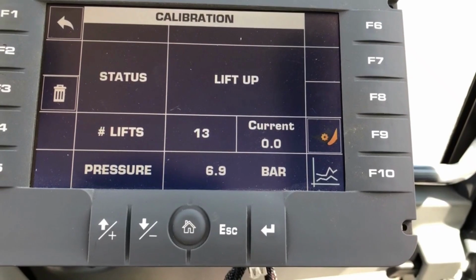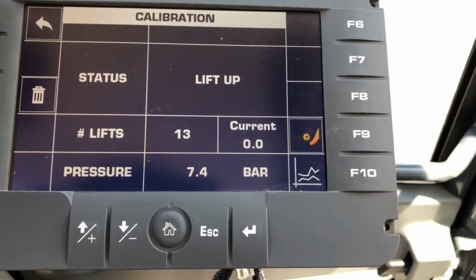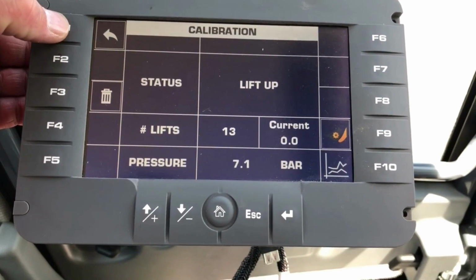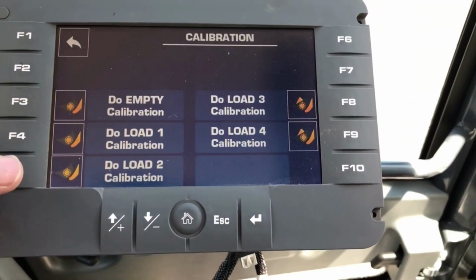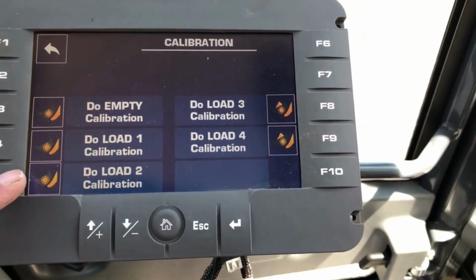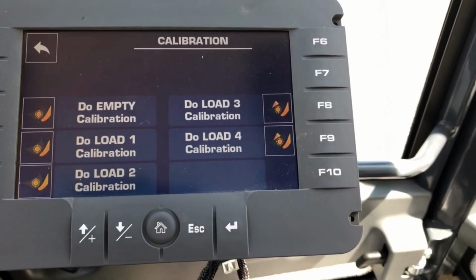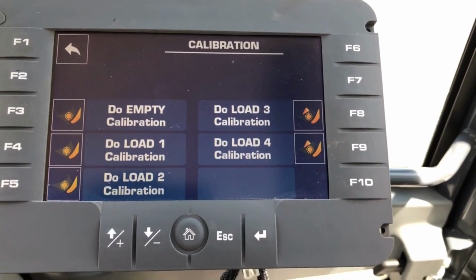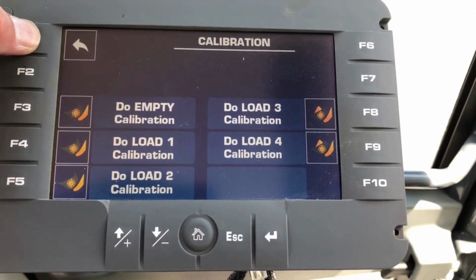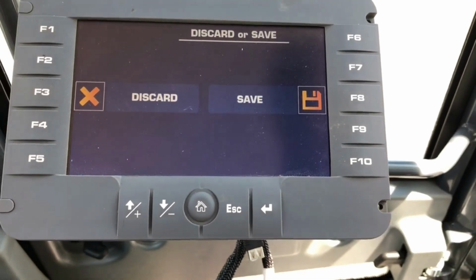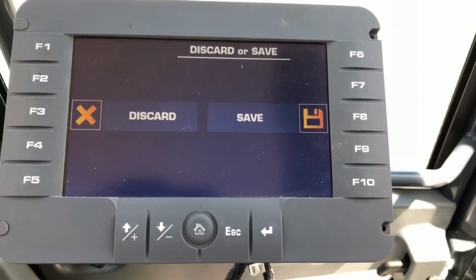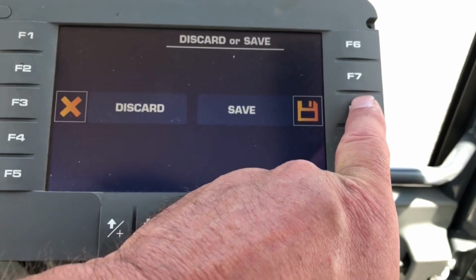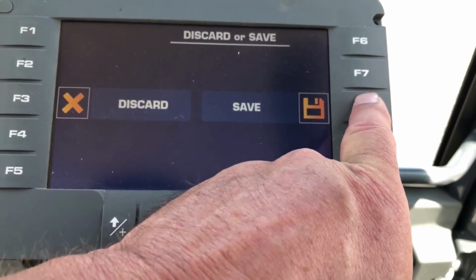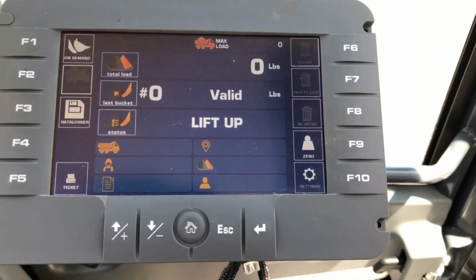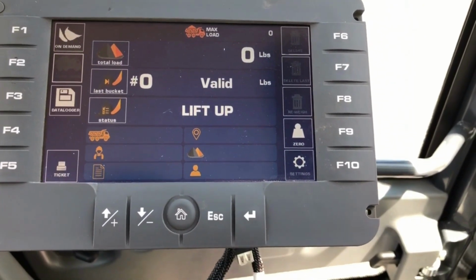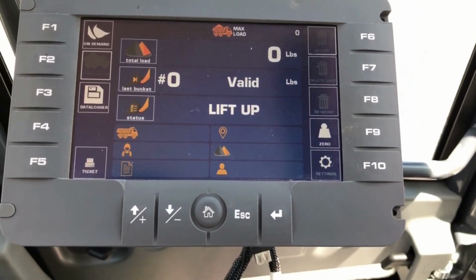And then you would continue doing all your lifts, and then hit your F1 to go back, then continue on, do your load 2, your load 3, your load 4, and then once you're done with that, you can go to F1. It's going to ask you if you want to discard or save. We want to save the calibration, so hit F8. Once it's done that, you now have a calibrated scale.